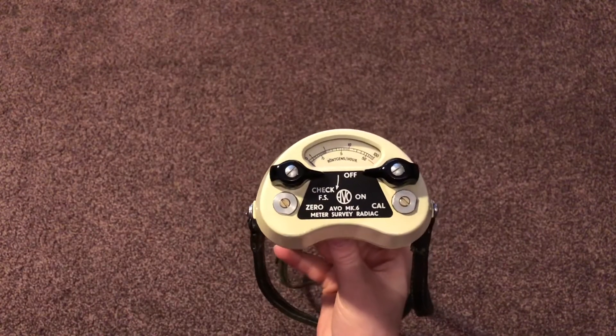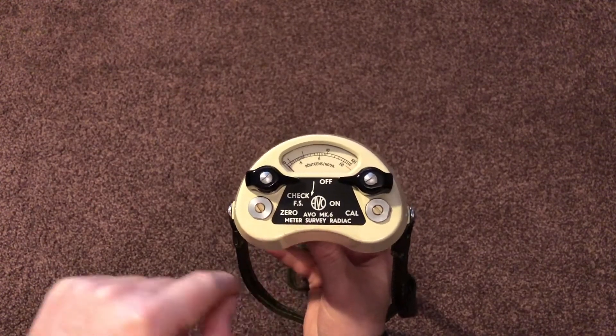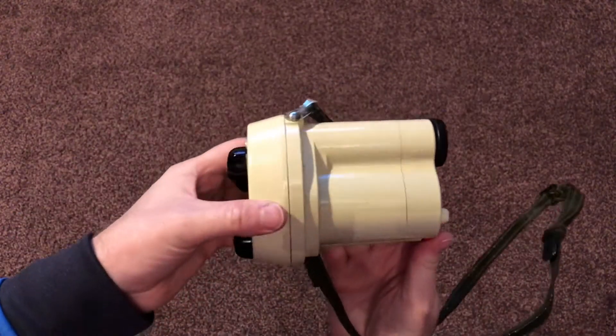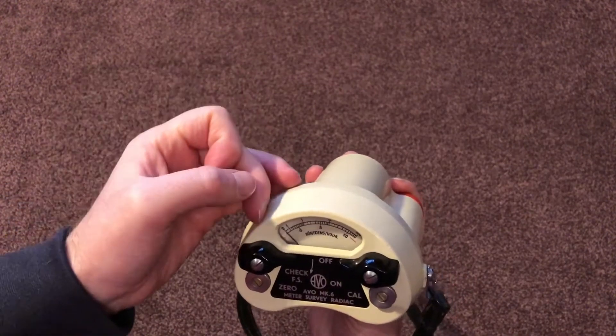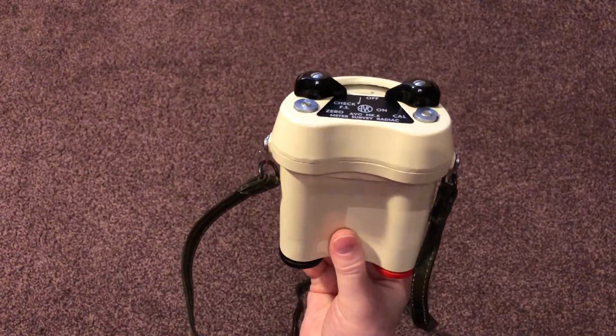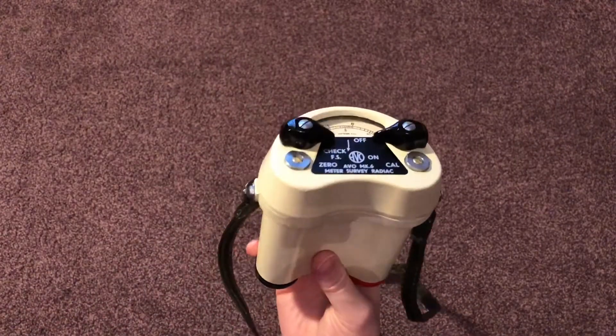We're going to start off with this nice little unit. This is made by AVO, the same company that made the original series of fixed survey meters. This is a Mark VI — an AVO Mark VI meter survey radiac. This little handheld meter is sometimes called a kidney meter because of its shape. It's scaled in röntgens per hour, going from 0 to 100 röntgens per hour, so it's a reasonably high-level handheld meter. This would have been the very first portable, easily transported lightweight meter that the Royal Observer Corps would have used for mobile monitoring.